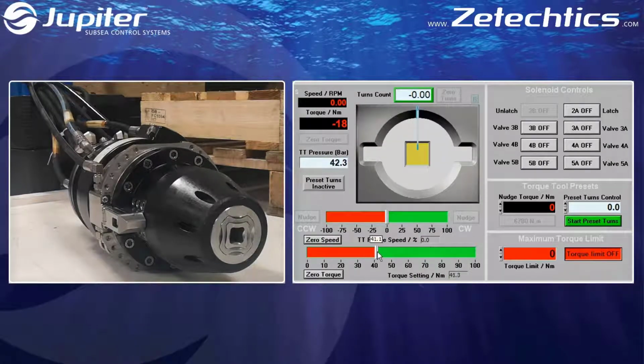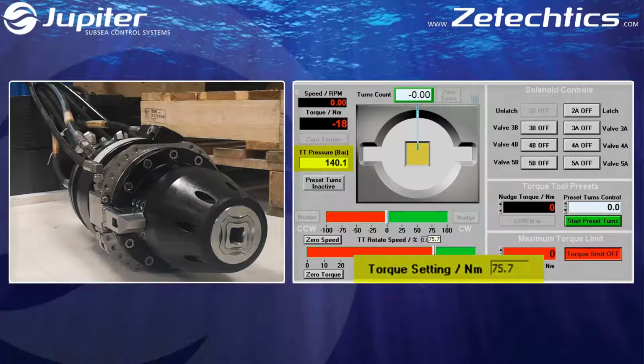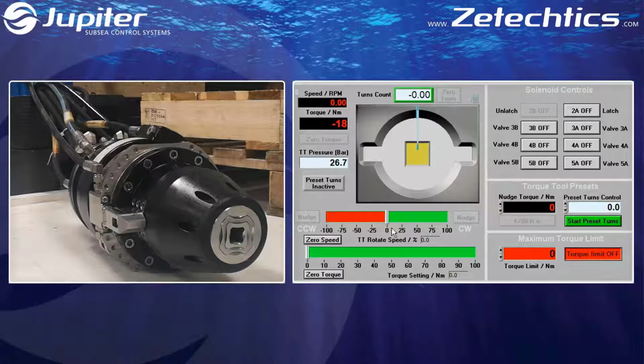Operate only the pressure valve again, taking note of where the control provides maximum tool pressure. We can see that almost 200 bar is now achievable. Proceed to test the remaining functions. Ensure the correct function occurs with each valve operation. If they are wrong, it is most likely the hose connections do not match the setup file. This can be corrected by moving the hoses or making setup file changes.